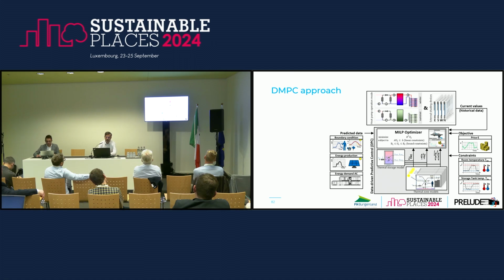How will our DMPC approach work? So that our approach can work, we need information from the experiment. We need from the building and from the technical building equipment current values and also historical values. With the historical values, we can parameterize the gray box models which we used. One model for the storage tank, and for each thermal zone, we use a gray box model. So we have 9 thermal zones, and we therefore used 9 gray box models, and all of the parameters of these gray box models we have to parameterize. So we use the historical data, more or less the last 42 days, to parameterize these gray box models.